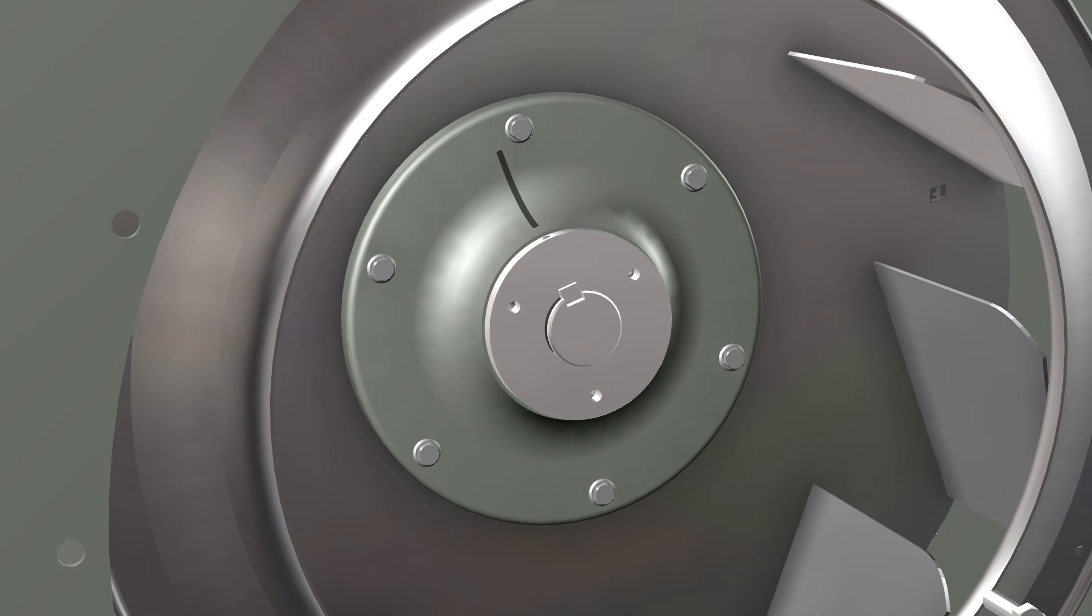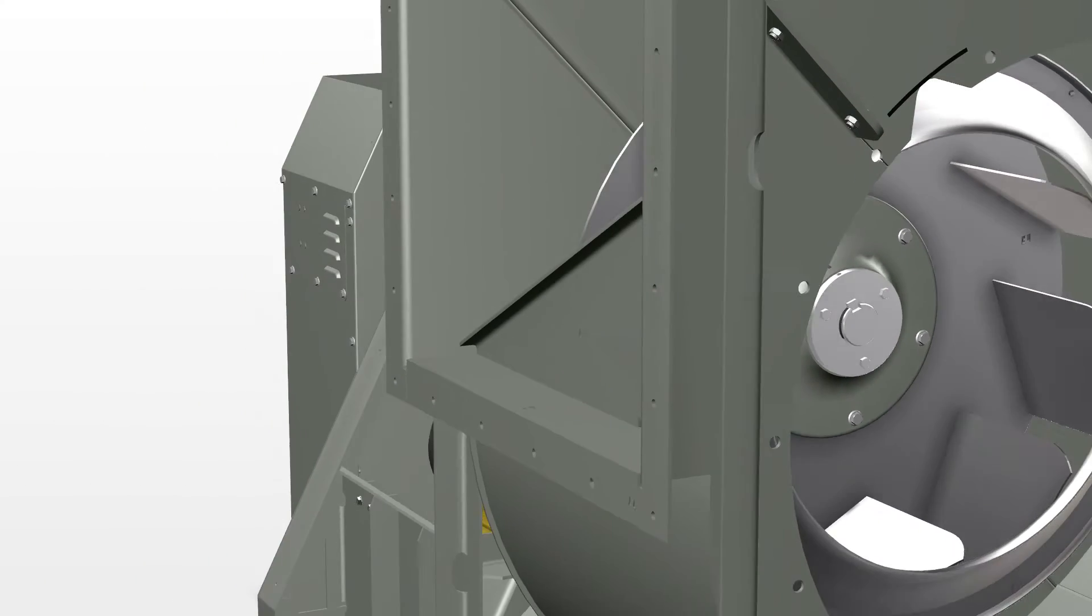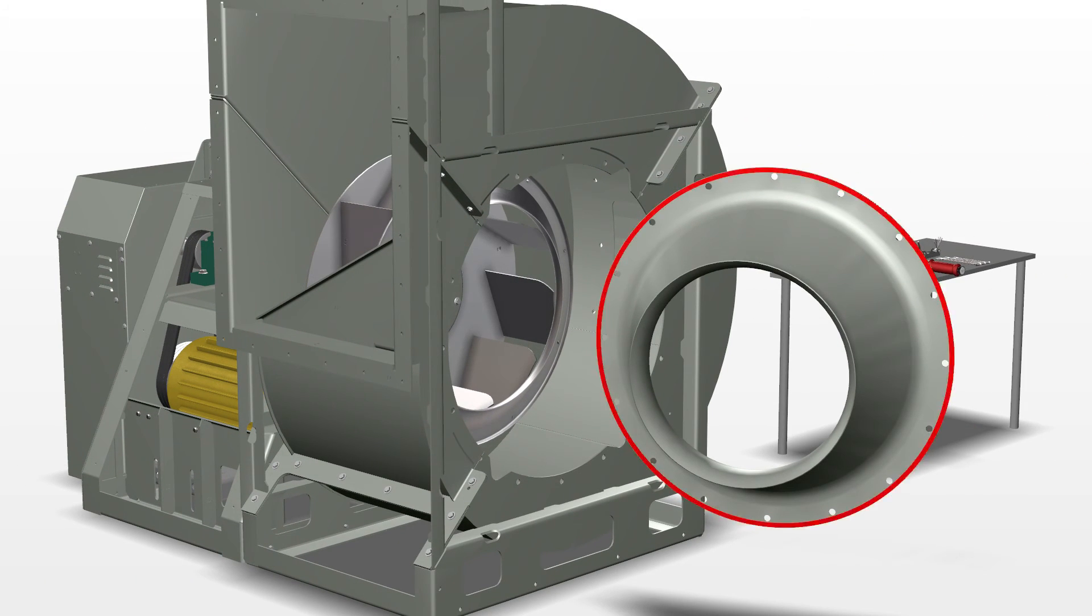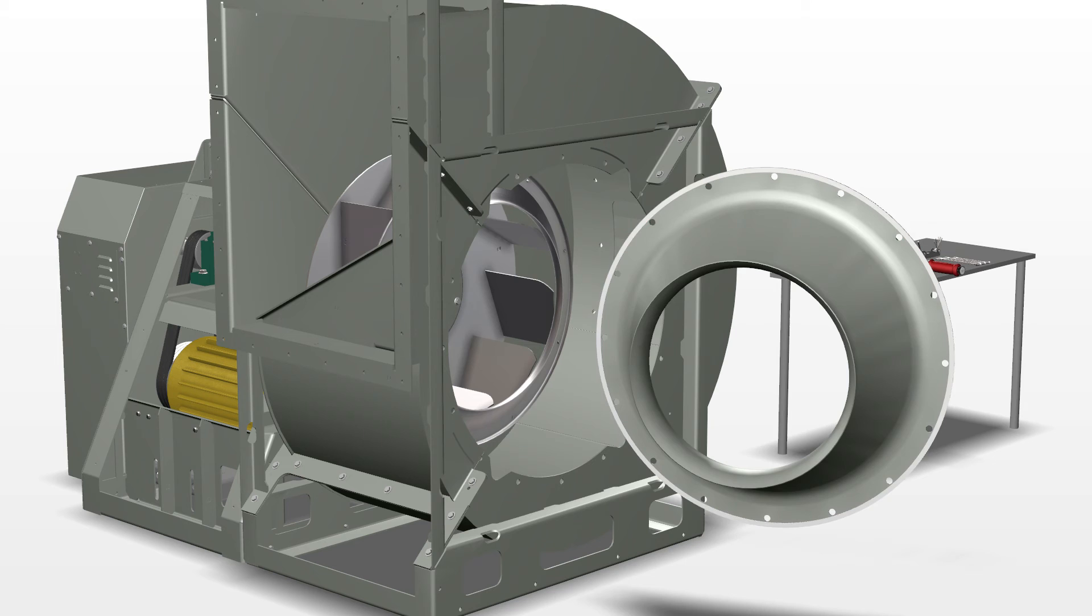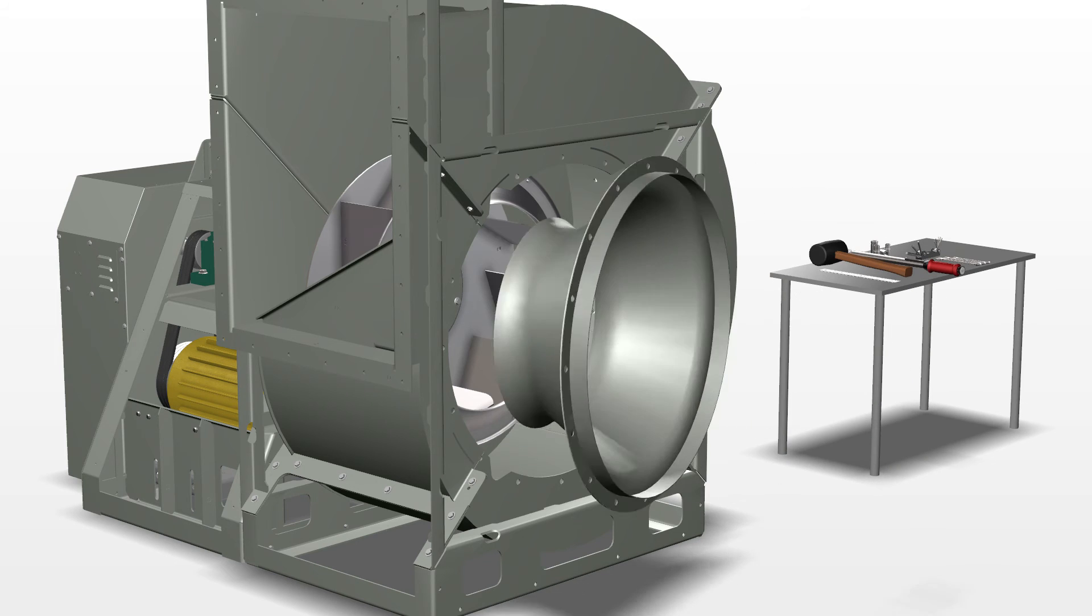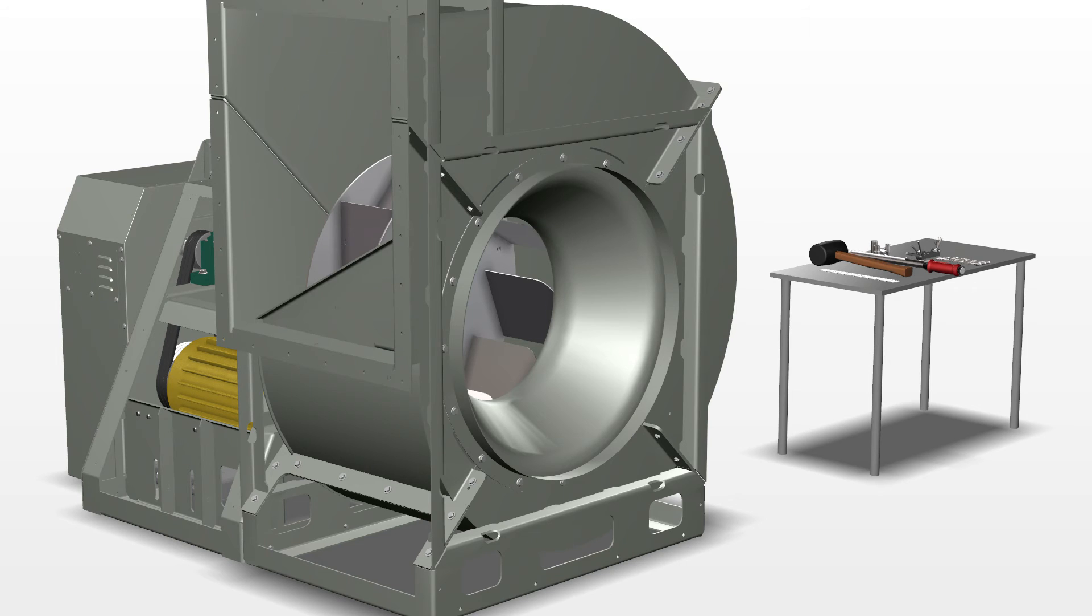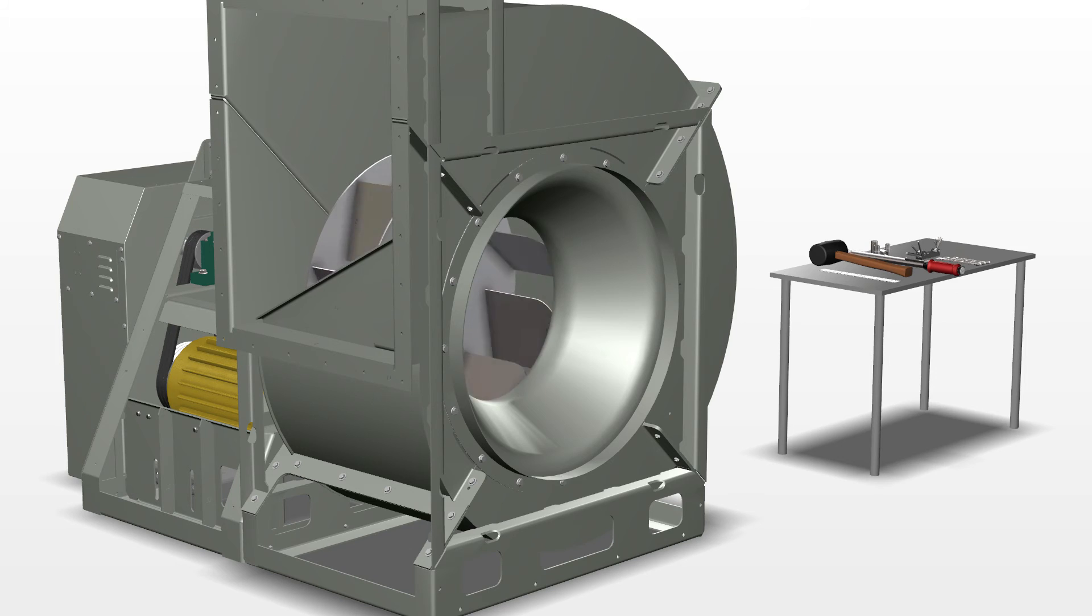Ensure the sealing tape is intact and undamaged, then install the cone leaving the bolts loose enough to align the cone with the marks on the housing or evenly spaced within the wheel. Rotate the wheel to make sure it does not rub on the inlet cone. Tighten the inlet cone bolts.